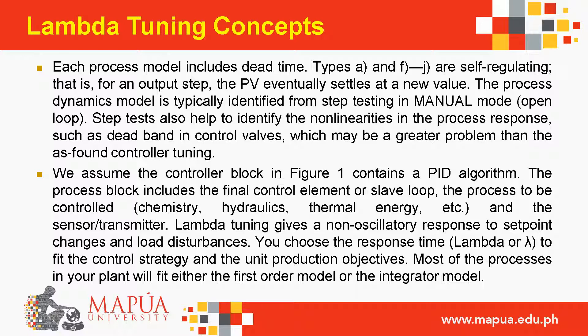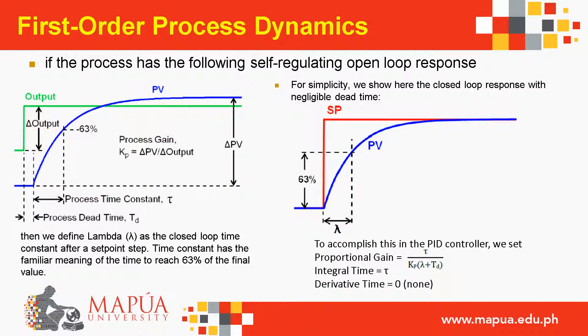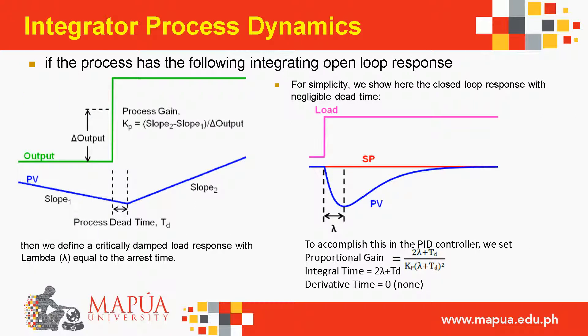The controller block contains a PID algorithm; the process block includes the final control element or slave loop, the process to be controlled, and the sensor or transmitter. Lambda tuning gives a non-oscillatory response to setpoint changes and load disturbances. You choose the response time lambda to fit the control strategy and unit production objectives. Most processes fit either the first-order model or the integrator model.